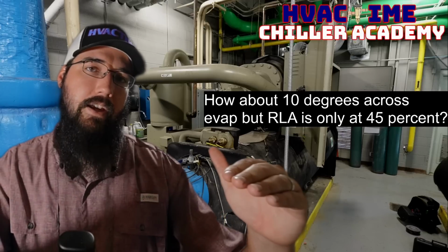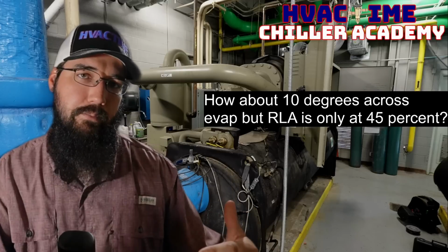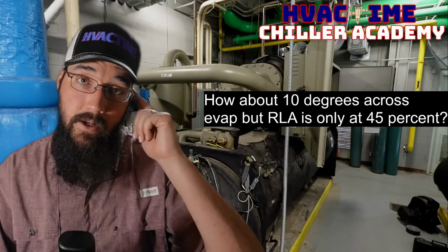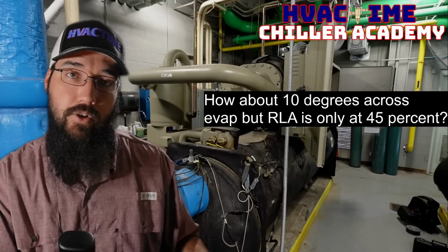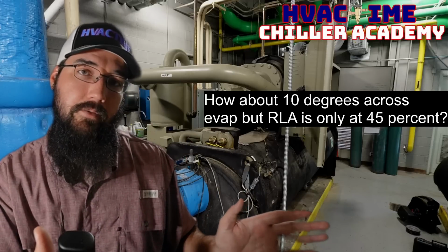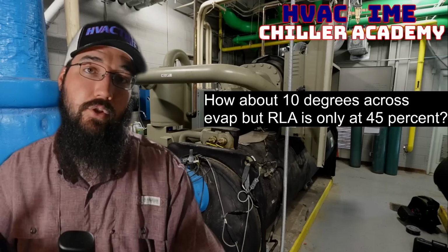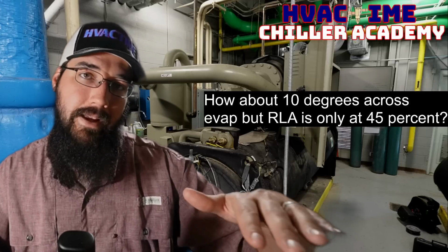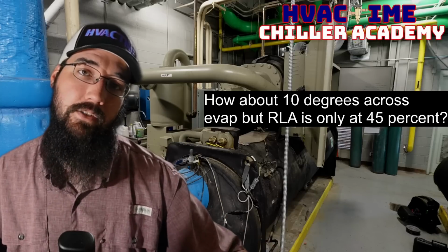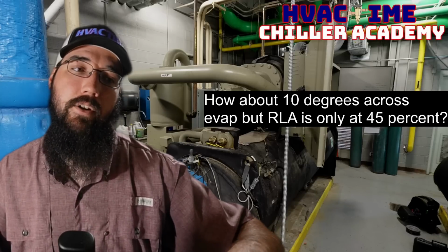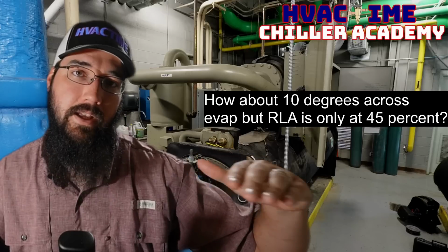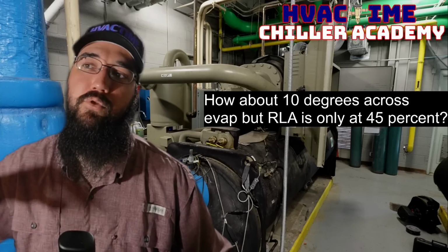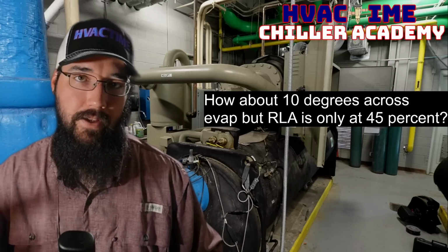by raising that condenser water set point, yes, we go from pulling 20 amps to 40, 50 amps on the motor, but our chiller in turn goes from doing 100 amps to 150, 200 amps instead, because where we could maintain really low condenser waters and maximize the chiller's efficiency, instead we are forcing the chiller to run at a much less efficient state by having higher condenser water, just so that we can save a few amps on the tower fan.